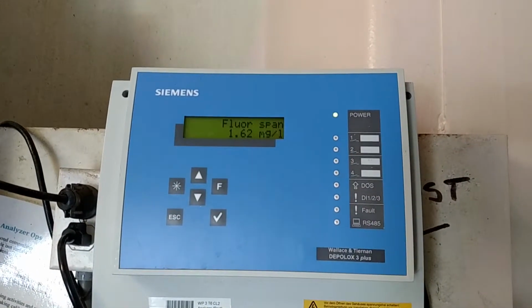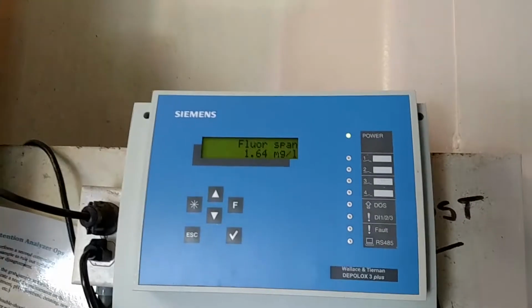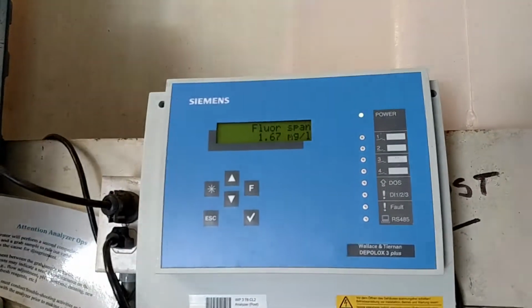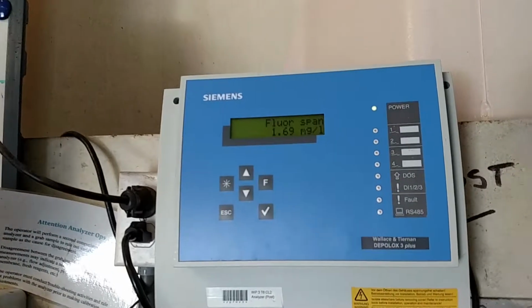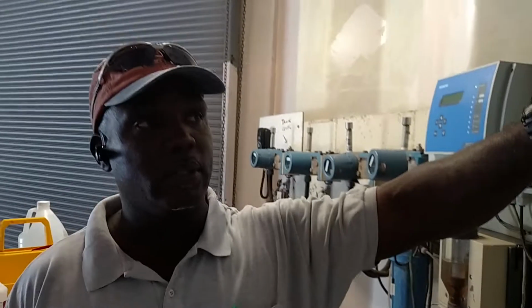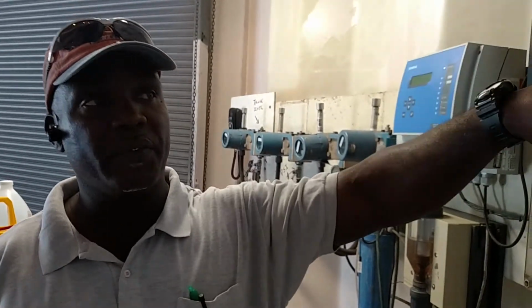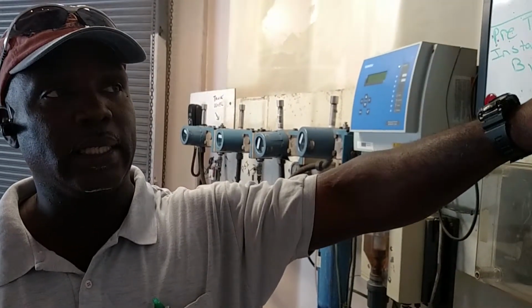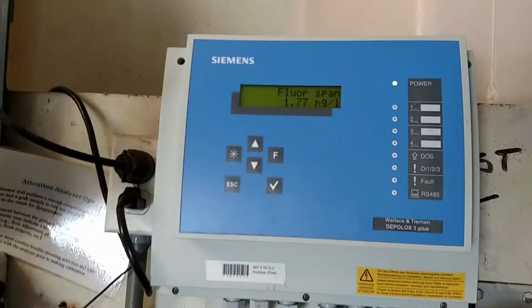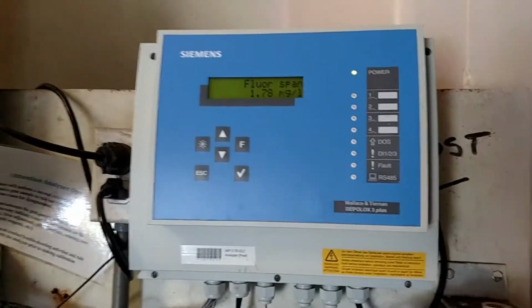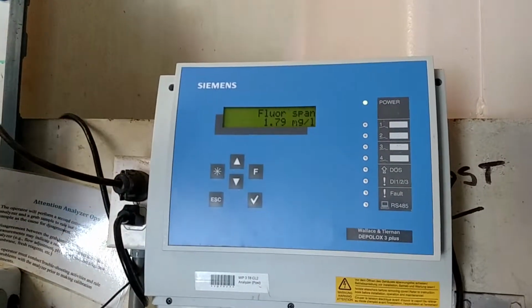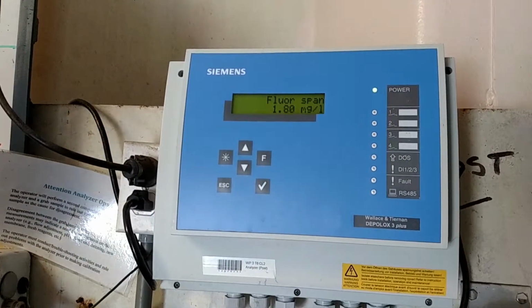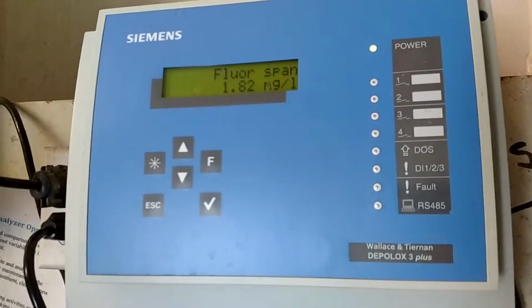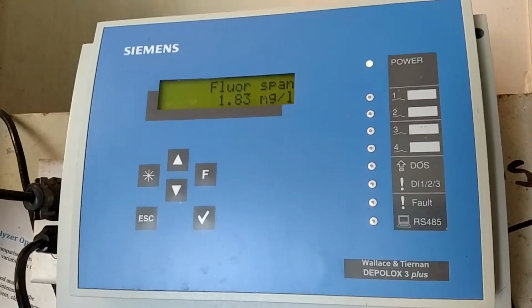With the new ones you put on, you normally have to do an initial calibration, and then more of a trim calibration after about 24 hours. But if it's going up fast like that, you just let it do its thing and finish it up. But if you see it's going real slow, and after 5 minutes it's only like a 0.9, either the probe is out of calibration, or it needs to be conditioned, or it could be bad.